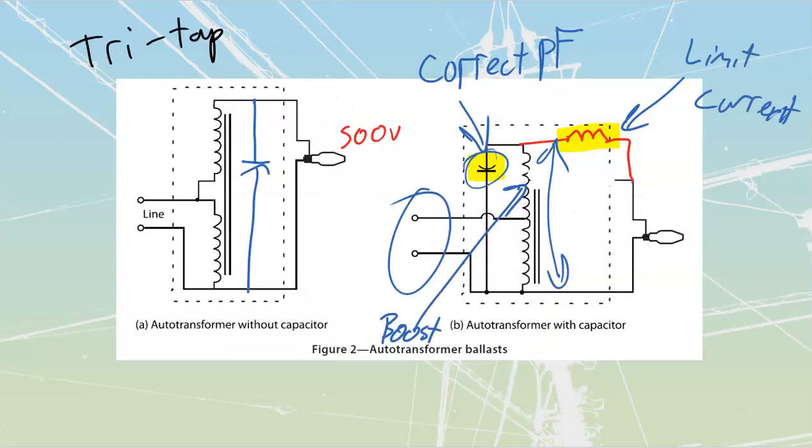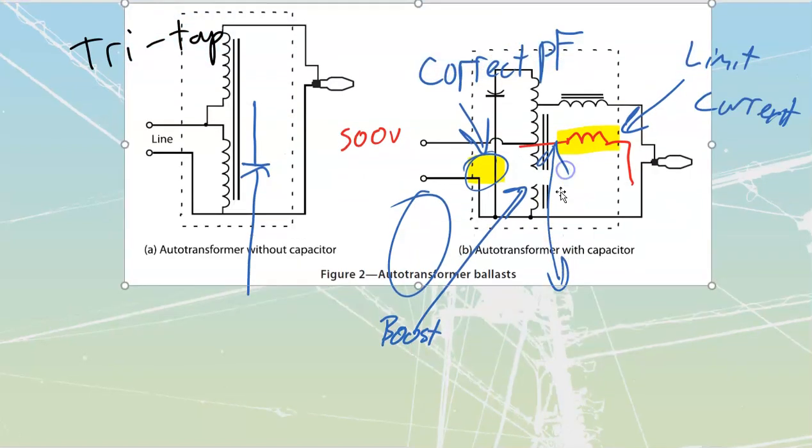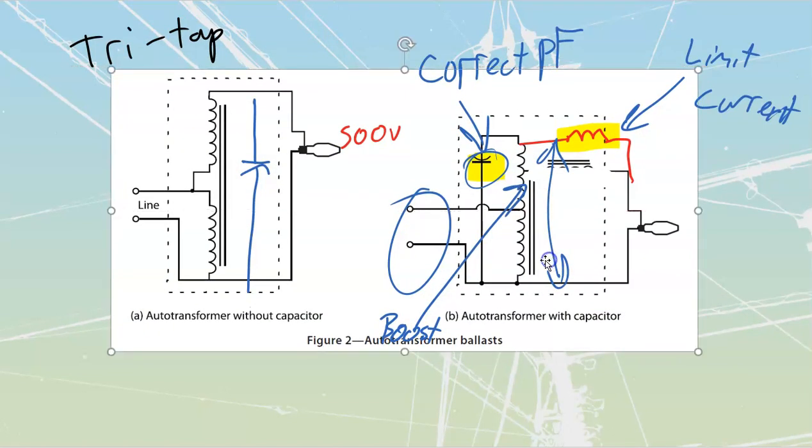With the previous ones that we looked at, my autotransformer, we were limited to supply voltage variations of 5%. We could go up to 105 and drop down from 105 to, you know, 95 as well, and that was going to be fine. It wasn't great for it, and I could have instantaneous short dips that would go as far as, you know, 15 or 20%.